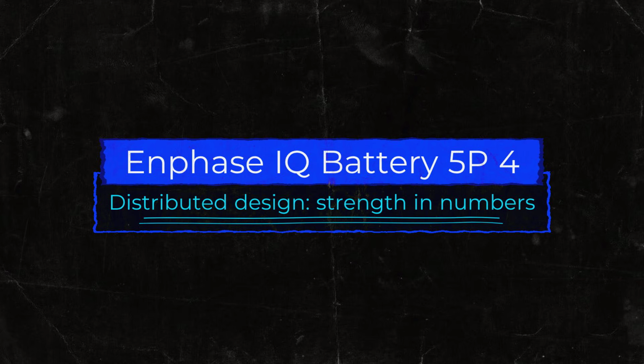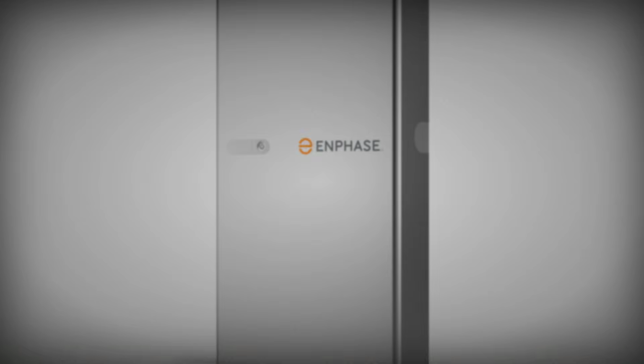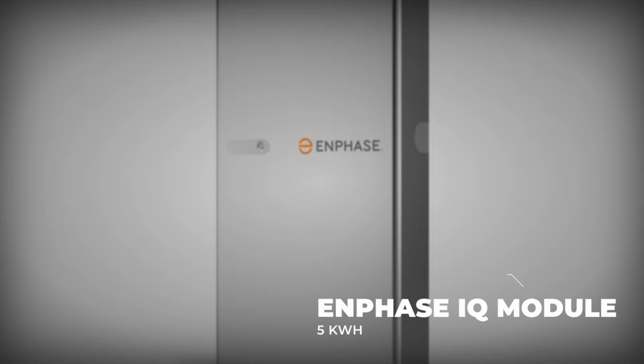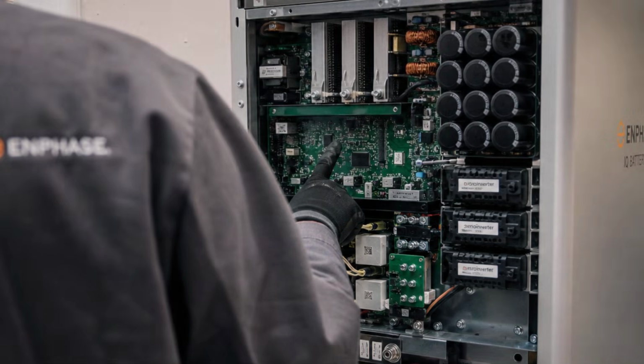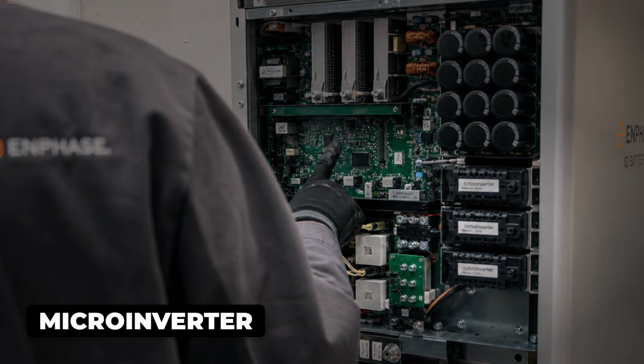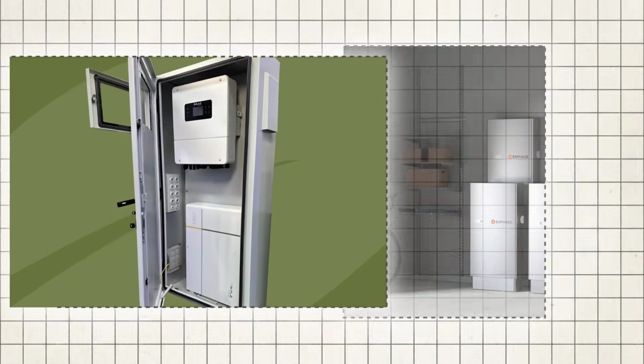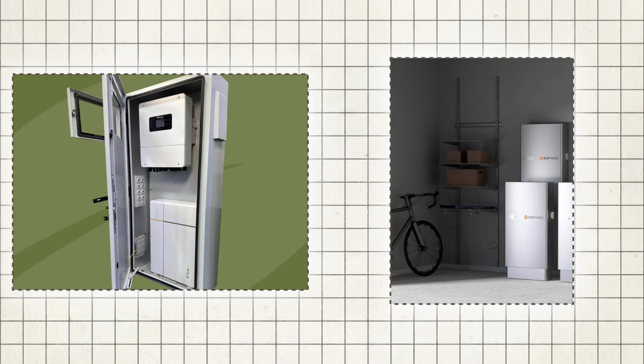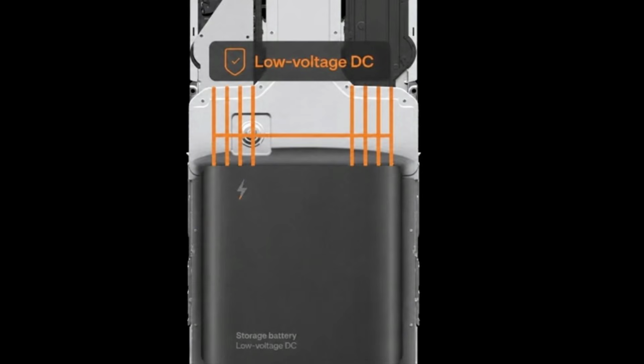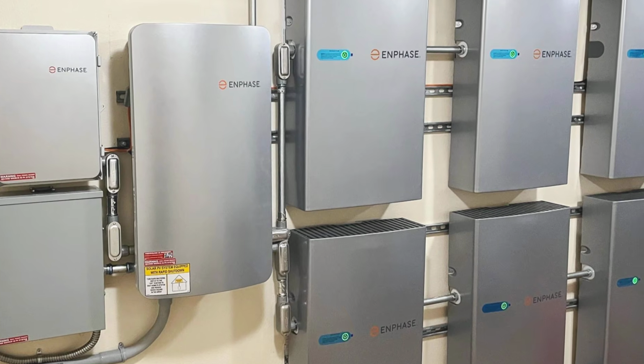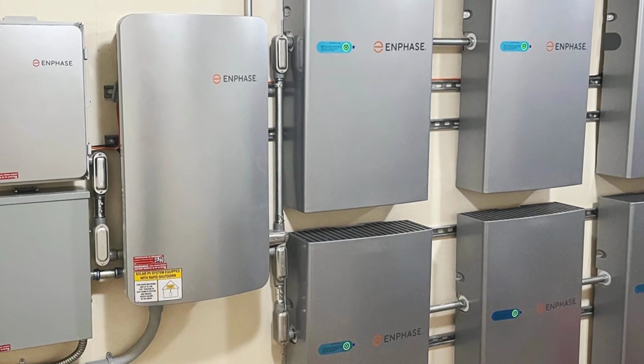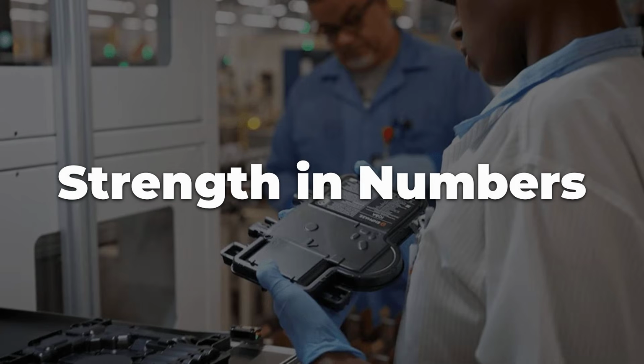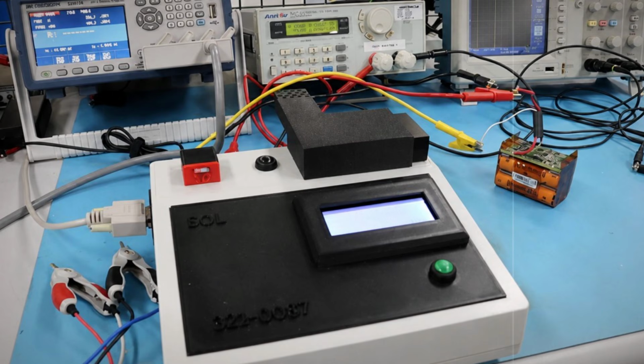If you've seen one of these installed in a garage, it doesn't look like one big battery at all. It's a stack of smaller boxes, each holding 5 kilowatt hours, each running its own built-in microinverter. That's the whole point. Instead of one big battery and one big inverter that both have to work perfectly, Enphase spreads the risk across 6 microinverters inside each module. If one has a problem, the rest of the system keeps running. That's a genuinely different approach to reliability, not just a marketing line.